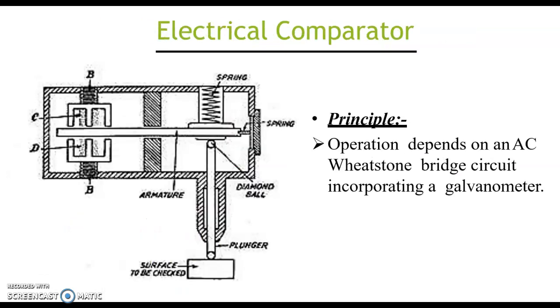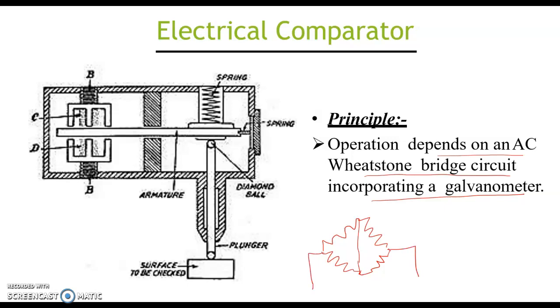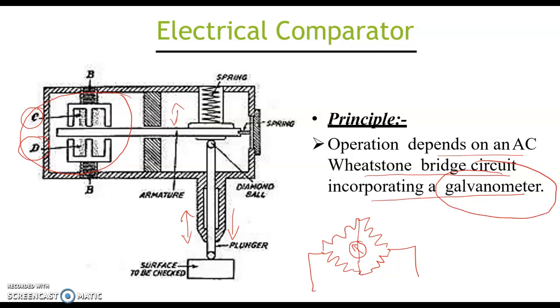In an electrical comparator, the operation depends on an AC Wheatstone bridge circuit incorporating a galvanometer. The Wheatstone bridge is constructed using C and D coils with an armature in between, which is connected to the plunger. Whenever the plunger moves, the armature position changes, varying the current induced in the C and D coils. This variation in current is measured by the galvanometer, whose needle or dial is calibrated to show the displacement.